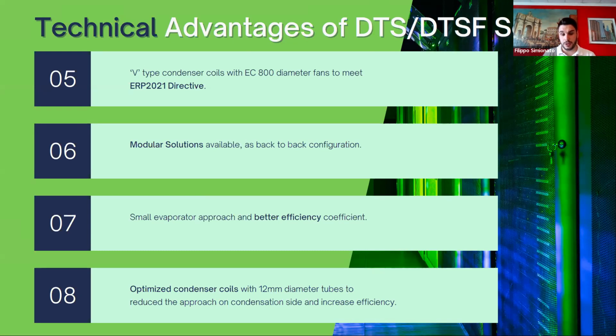of refrigerant in each refrigerant circuit. Of course, when designing a new series, it is also important to focus on the efficiency of the unit. So we look not only at our suppliers of main components, such as the condenser coil or evaporator, to get the best efficiency possible. This is why the approach, for example, on the evaporating side is 2.5 to 3 degrees, and the optimized condenser coil with 12 millimeter diameter tubes allows us to reduce the refrigerant charge. There is also the possibility to use a microchannel condenser coil, and of course, to reduce the approach on the condenser side to get the best efficiency possible.